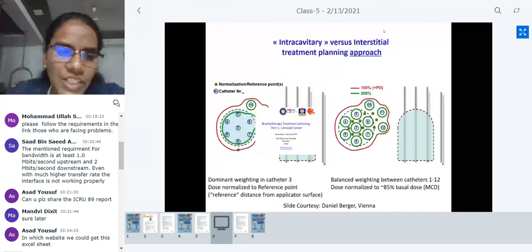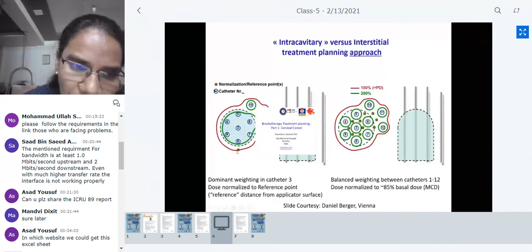So if it is going to be interstitial, you are going to define these source points, and these are all the basal points here. And your 200% is just around the needles, and your 100% is actually covering the entire implanted volume. On the other hand, if it is going to be only intracavitary, then you are going to position a point here at the surface of the applicator, which is the vaginal cylinder, at 5 millimeter. And from here, you use this point as a normalization point. So you can see that 200% is the continuous line inside the applicator, while your 100% line is also continuous, similar to that of interstitial. So this is a major difference between intracavitary and intracavitary plus interstitial.